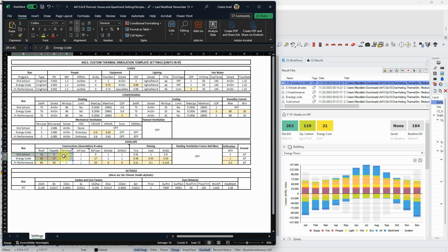The energy code iteration, and here you have a U value of 0.45 in your glass. That's an R value of 2 in IP units. That's really pretty bad. So we're going to get a lot of heat loss in the winter and gain in the summer that's not related directly to the sun. It's just going to be the temperature outside.